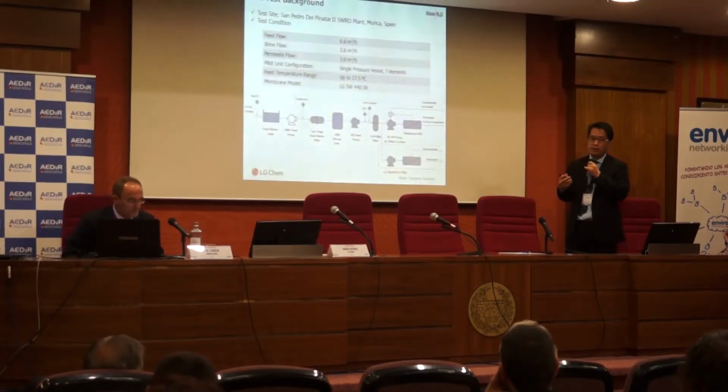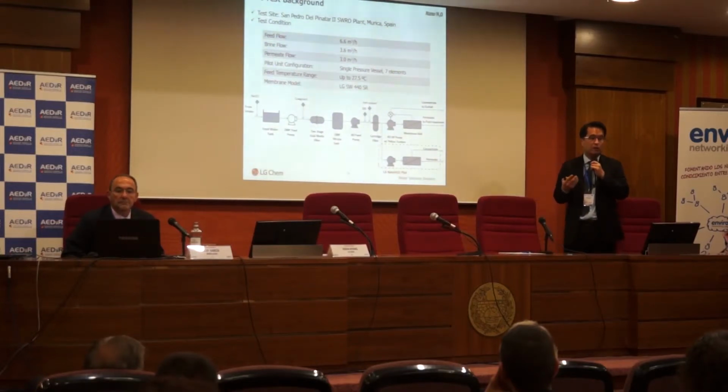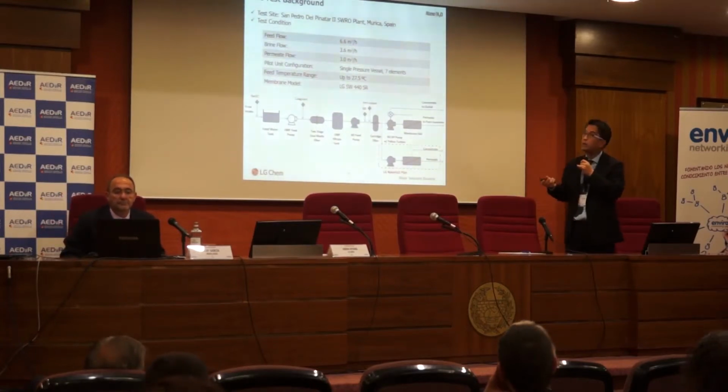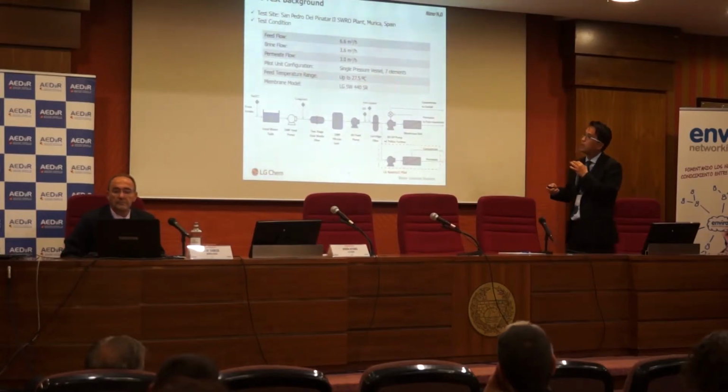To verify the actual boron removal of our CORE RO membrane, we did some pilot testing in Spain. The plant is the San Pedro del Pinatar 2 SWRO plant, located in Murcia, Spain. The test condition was pilot scale, so we just used one pressure vessel with 7 elements of our standard SWRO 440 square foot membranes, and permeate flow is 3.0 cubic meters per hour with 45% system recovery.